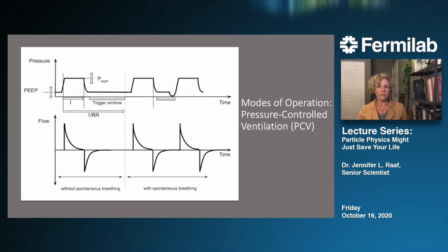Now, as it happens, patients who are not capable of breathing on their own still sometimes will take spontaneous breaths. And if you didn't allow that to happen, it would be a moment of torture for the patient. And so the MVM software is written to allow patients to take a breath anytime during the exhalation. So that's what you see with that little downward dip on the new waveform that appeared on the right side.